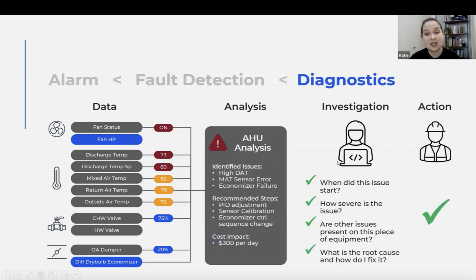Now, fault detection and diagnostics will help you get over that finish line. So you'll say, I know when the issue started. I know how severe it is. I can even put a cost to it. I can say it's $300 per day if I let this continue. I can tell if there's other issues present on this piece of equipment and potentially other pieces of equipment. If my air handler is in fault, are my VAV boxes that are impacted by that air handler also in fault? And then it also helps to tell you the root cause.